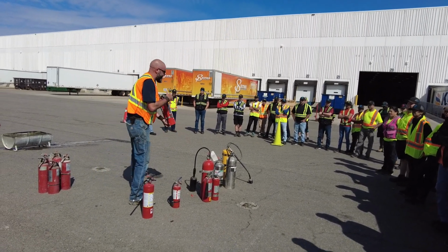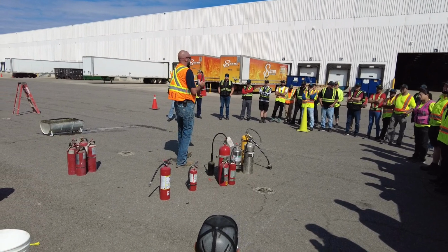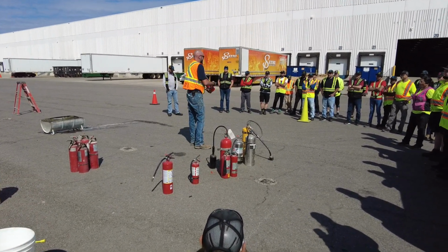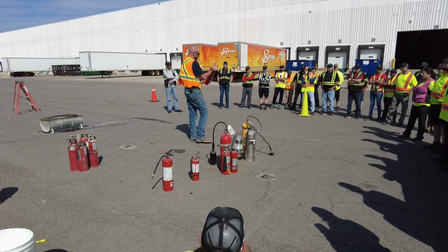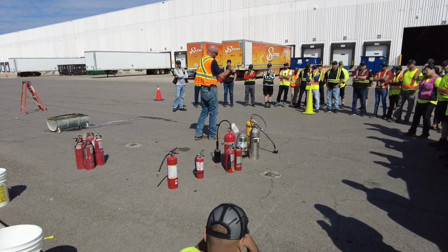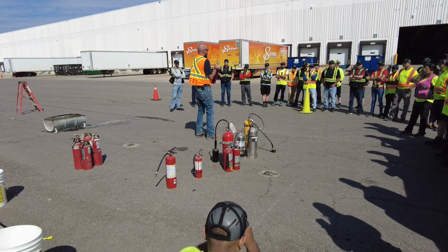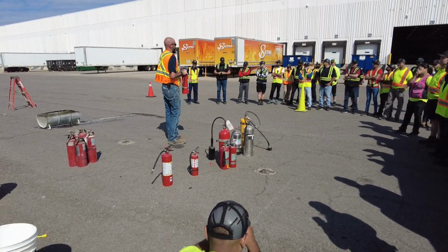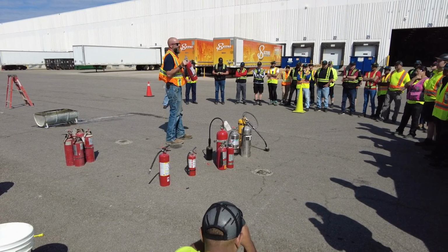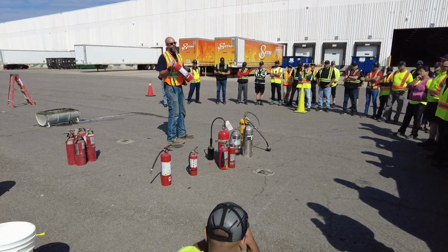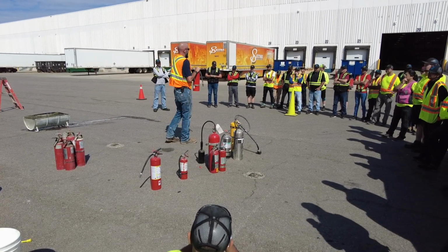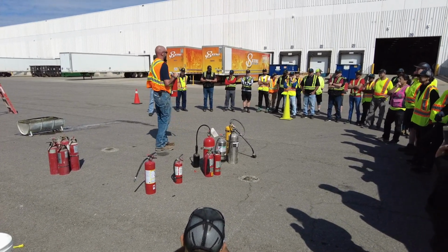This one again looks the same, but it's got a purple label. This one's purple K. Again, it's only rated for B and C type fires, and this one is potassium bicarbonate. So we're using all sorts of different chemicals for different firefighting applications. This one you're only going to see probably around fuel stations, big fuel supply depots. It probably works better on fuel fires.